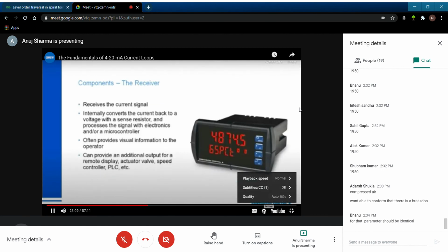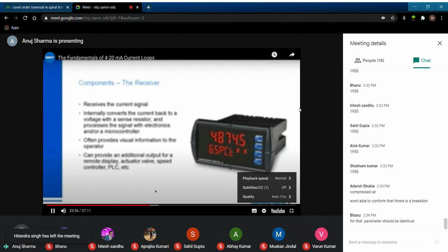Then you've got the receiver or receivers. The job of these is to receive that current signal. These are your panel meters, your chart recorders, the inputs into a PLC, the input cards on a SCADA system, essentially anything else that is reading that current loop. And usually what these will do is internally, invisible to operators or installers, they'll have some kind of small sense resistor.